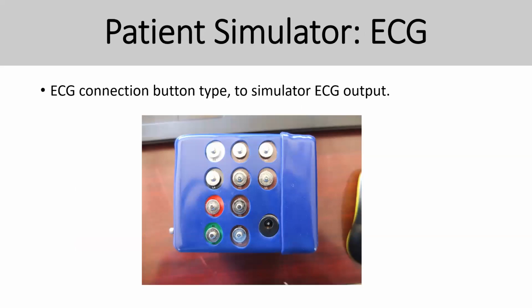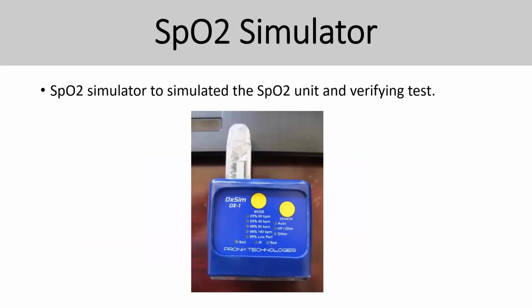So this is the patient simulator part. These are the ECG connections, button type, to connect all these particular things. So 10 particular leads are connected here to measure the 12 lead. The SpO2 simulator I use to measure SpO2 sensor output. So you simulate the reading, for example, 99% saturation and heart rate maybe 85. By setting that particular reading, you're going to verify whether the patient monitor is getting the same reading or not.